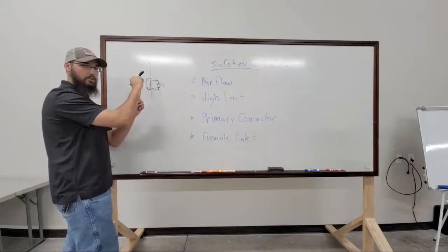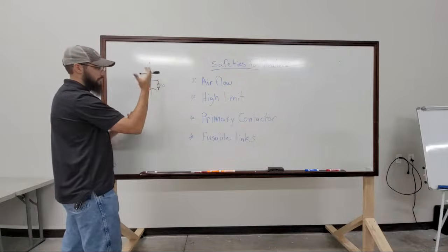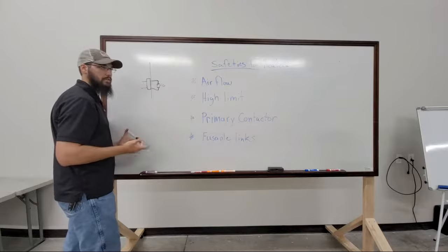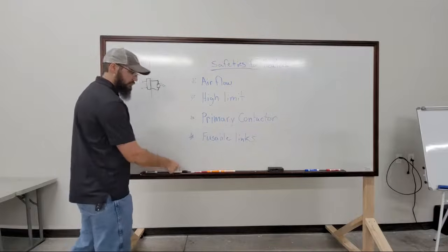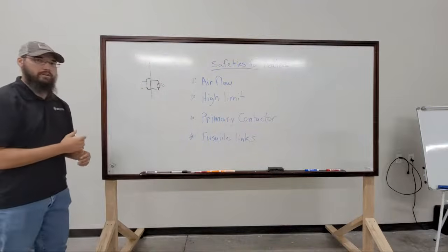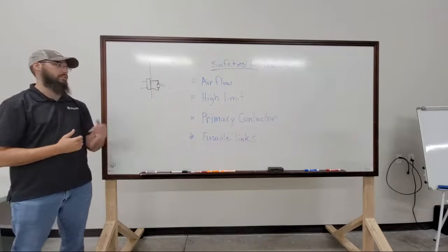You just test continuity through it. Then they're pretty basic outside of that. They're just killing the physical power. So even if the contactor's pulled in, the heat's not going to run if that fails.